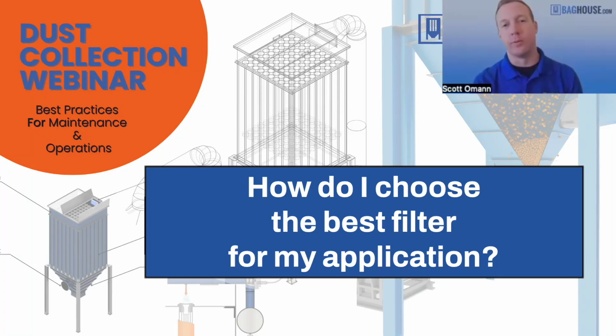Yeah, we don't have a one-size-fits-all approach. There's a couple of different things that we need to keep in mind when we look at our filter media or the fabric type. The first one that we would consider would be the temperature. Do we have a high temperature or a low temperature application? Low temperature would be anything generally up to 250 degrees Fahrenheit. High temperature would be anything above that, generally to about 500 degrees Fahrenheit.